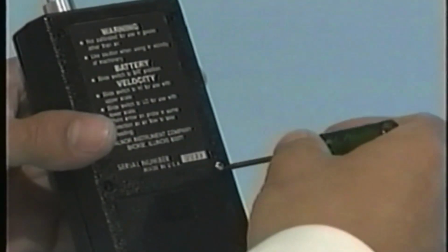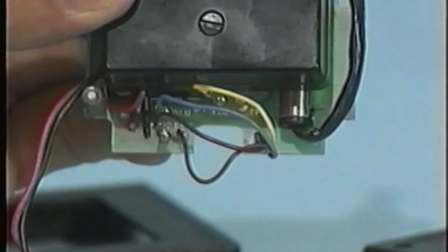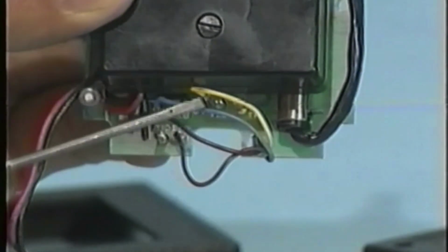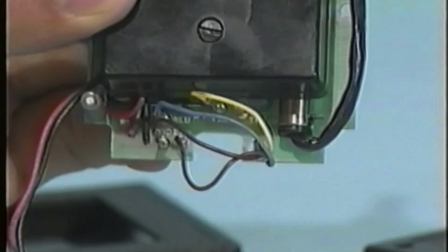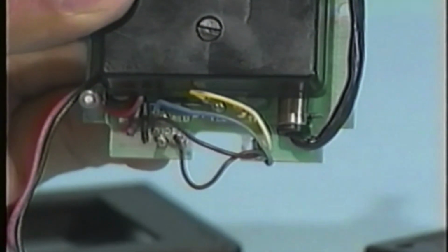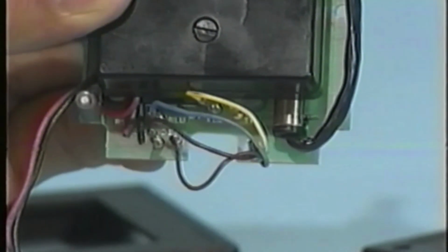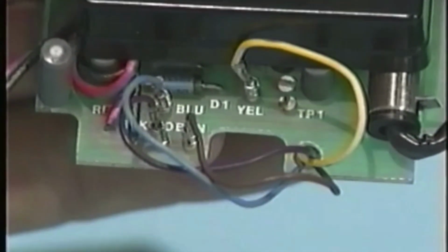In case of a broken probe, open the instrument by unscrewing the 4 screws on the back cover. Following this, disconnect the 4 wires from the probe and remove the probe, replacing it with a new probe. When connecting the probe wires, make sure to match the wire colors to the corresponding color labels on the board. Calibration of instrument is required after replacement of probe.